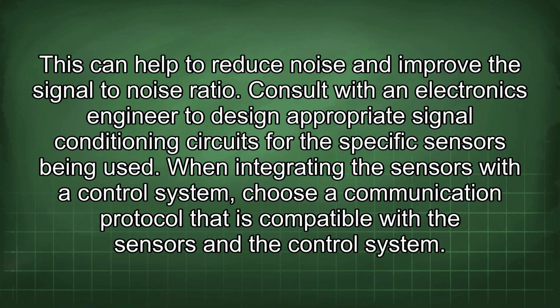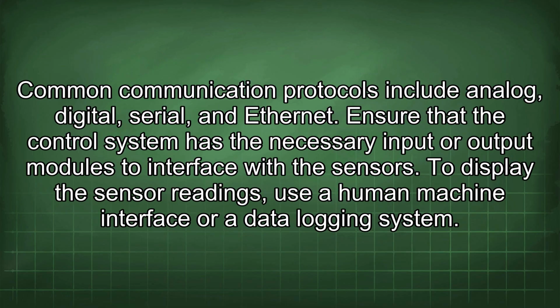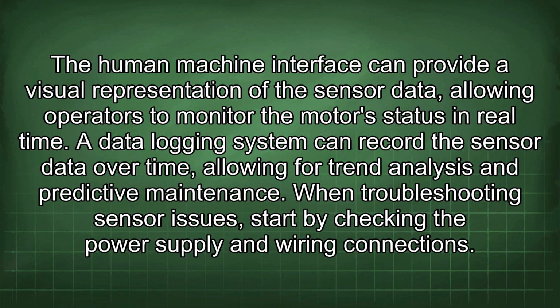When integrating the sensors with a control system, choose a communication protocol that is compatible with the sensors and the control system. Common communication protocols include analog, digital, serial, and Ethernet. Ensure that the control system has the necessary input or output modules to interface with the sensors. To display the sensor readings, use a human-machine interface or a data logging system. A human-machine interface can provide a visual representation of the sensor data, allowing operators to monitor the motor's status in real time. A data logging system can record the sensor data over time, allowing for trend analysis and predictive maintenance.